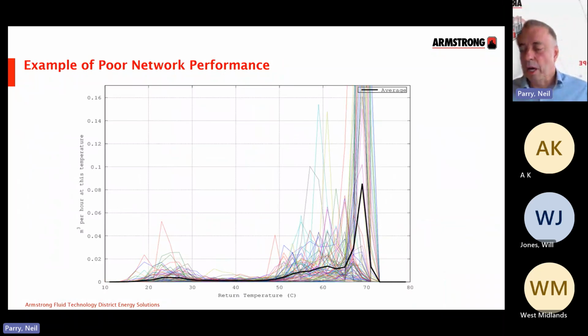So this is a histogram of a system which unfortunately is quite typical in the UK. The flow temperature on this project was 80 degrees C, and you can see the big spike at the end of the graph, which is measuring return temperature, at around 68 degrees. So typically a 12 degree delta T, which is really quite poor in today's heat networks, but unfortunately it's quite reminiscent of systems that we've been doing.